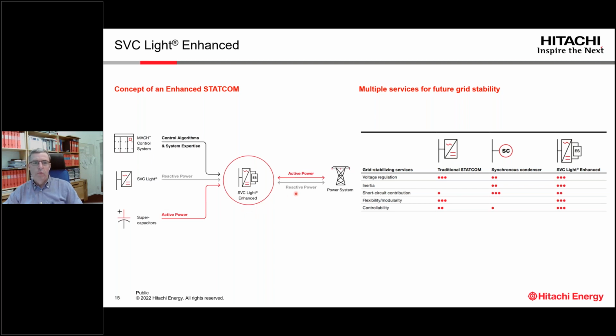And with this one, in addition to injecting and consuming reactive power, we can also play around with the active power. And when comparing now, how good is this? We could compare it with the traditional STATCOM and with the synchronous condenser. And here we have the SVC Light Enhanced. Then we see that this SVC Light Enhanced is better in all these cases here, except this one, short circuit contribution. Today, the synchronous condenser injects lots of current when we have a large voltage dip. And this overload current we cannot obtain with the converter today.